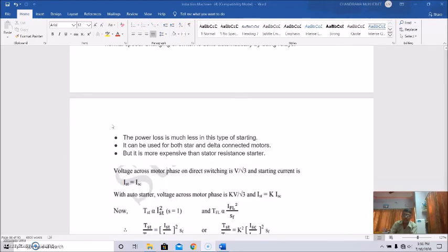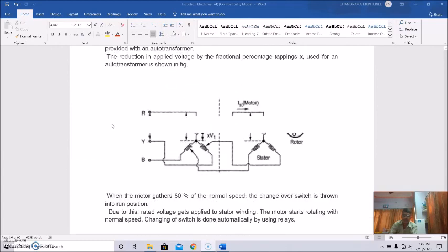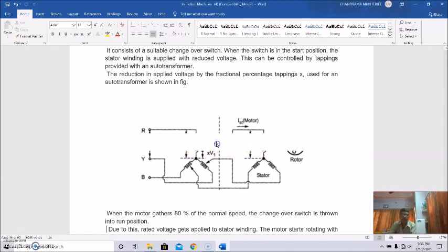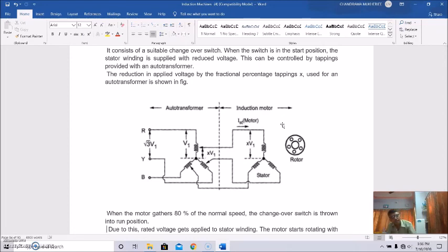Basically we started our discussion in the last class, that is on the starters, and in this class we have discussed the primary resistor starter, with its simplicity, but its power loss is more, though its cost is less. So in that case, we used the auto transformer starter to reduce this power loss. But its cost is more, and we can use any percentage of tappings to reduce the starting voltage. Though it is a very useful one, it is not the cheapest.